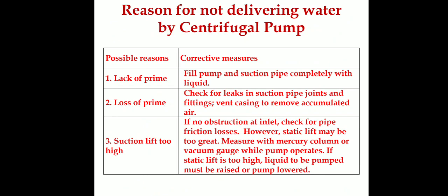Suction lift too high is another big problem. For a centrifugal pump, the suction height is optimized for around 6 meters. Exceeding this will reduce energy efficiency. We must adjust the height and level correctly.